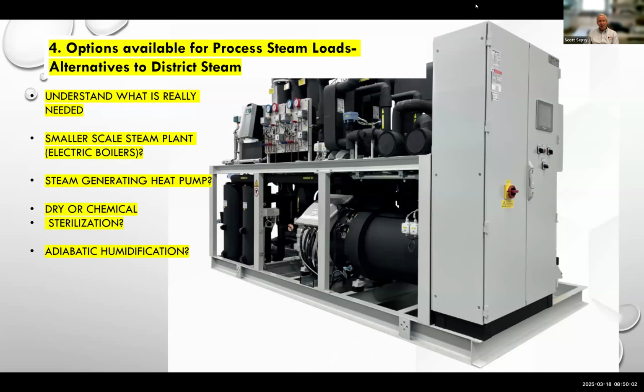So objective number 4 is talking about process steam loads, alternatives to district systems. If you want to get completely off steam, you got to understand and deal with process loads. These include autoclaves, cage washers, tunnel washers, sterilizers, and humidification. Examine the process. Is it right sized? For example, can wash down of cage be done at a lower temperature, pre-wash down? We did this and changed a process in one of our science buildings.